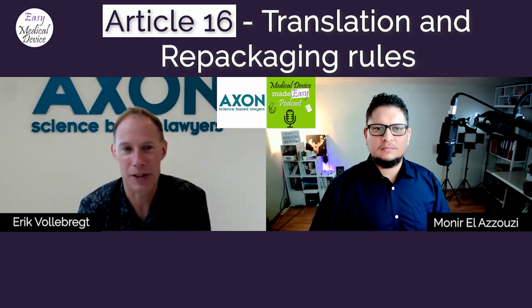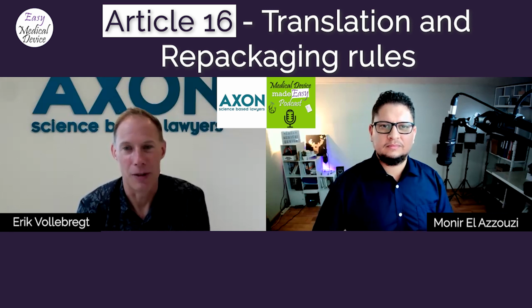There was the Roche versus Servoprax case at the European Court of Justice some years ago, where there was a dispute between Roche Diagnostics and a distributor about whether the distributor needed a quality system for activities that would be in scope of Article 16, Section 2, as it's currently in the MDR. The European Court of Justice at the time said no, it's not necessary, because these devices have been placed on the market. They are freely circulating.